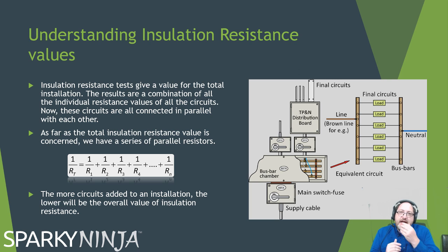The insulation resistance test gives you a value of the total installation. It's a combination of all individual resistance values of all circuits, and they are connected in parallel with each other. So when I test a fuse board, I'm testing the parallels of all the circuits that are on that board. If my reading is low, I can then break it down to test the circuits individually. But what I need to understand is that my resistance overall is the combined parallels of the system.